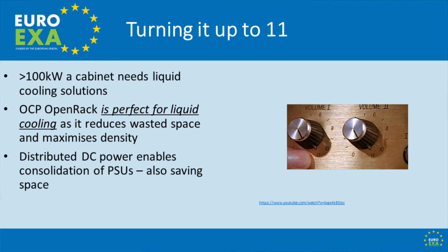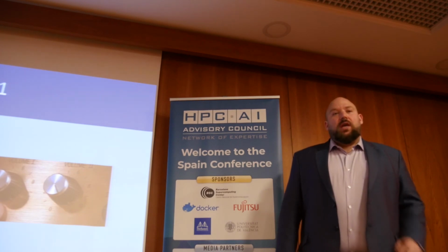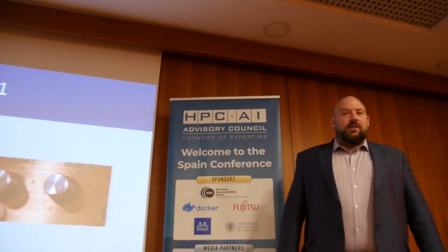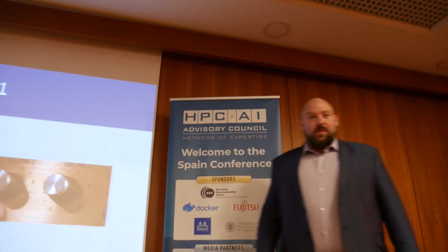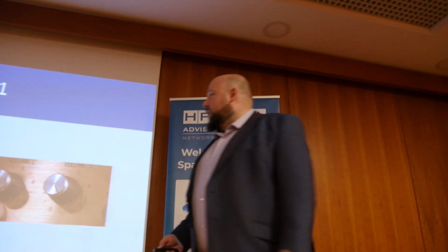We found that if we liquid cool the power supplies, we could make a power supply conventionally designed for a smaller power conversion capacity in air, and increase its power conversion capacity because it's better cooled. So we're able to look at power conversion in the region of 20 to 30 kilowatts a U for taking from AC to DC.